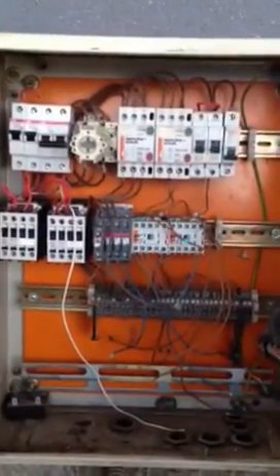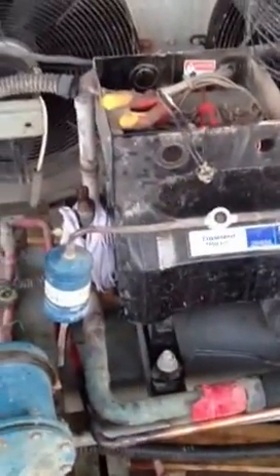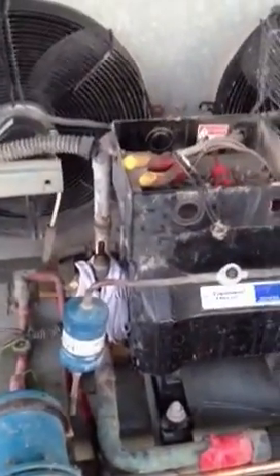So I'm going to redo the whole electric board. We're also going to give the unit a tune-up and an oil change, and I'm going to convert it from R-22 to R-404A, change the oil, and replace the expansion valve.